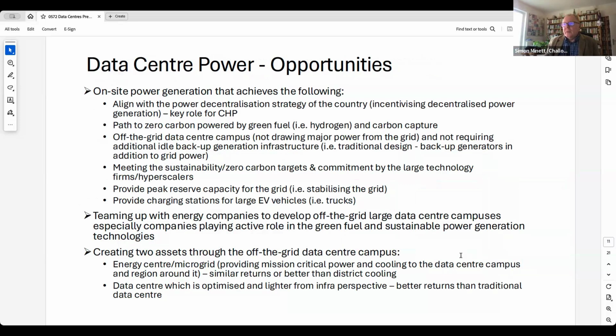Looking at the opportunities here, I picked three big ones. First is on-site power generation - it's almost a must for some sites because you won't get a grid connection. It's a significant opportunity for things like CHP to supply both the power and avoid using electricity for cooling, at least most of the time, using the waste heat off the engines to provide that cooling through absorption chilling.